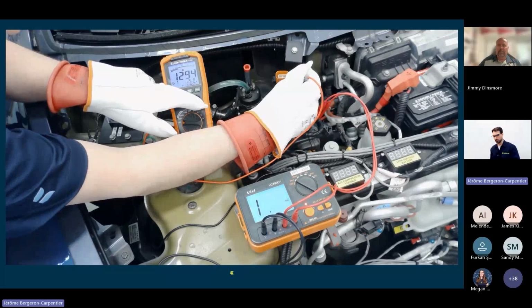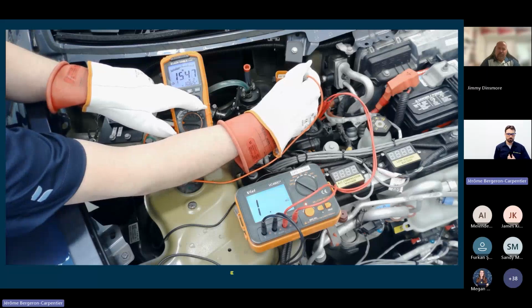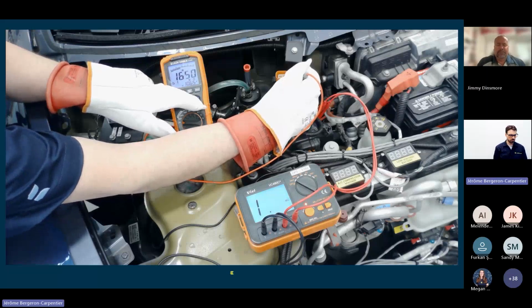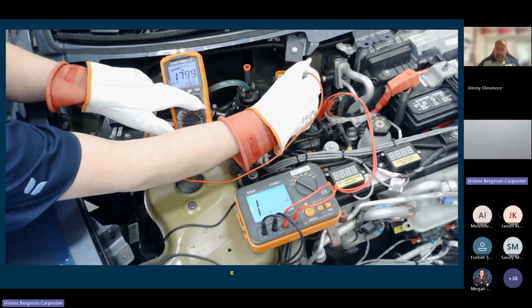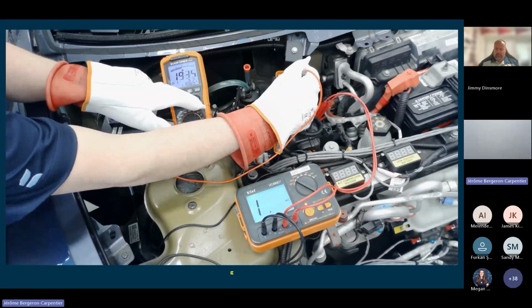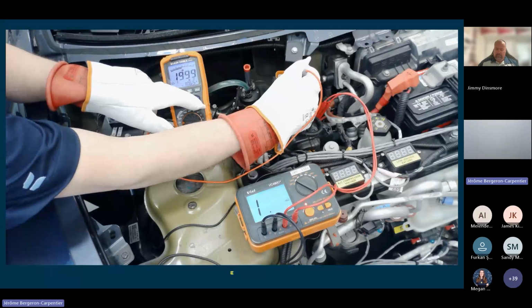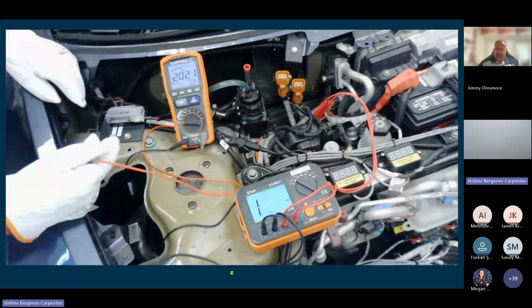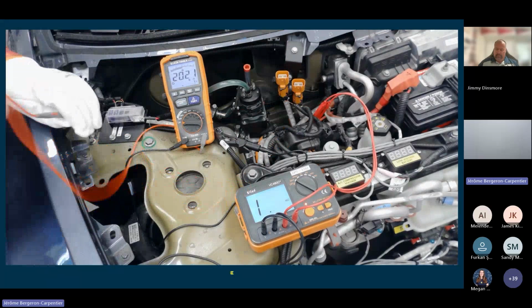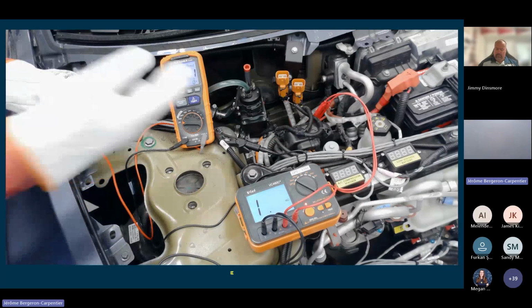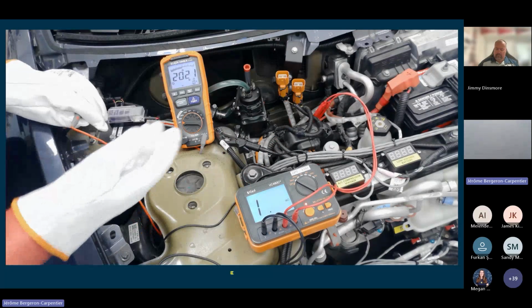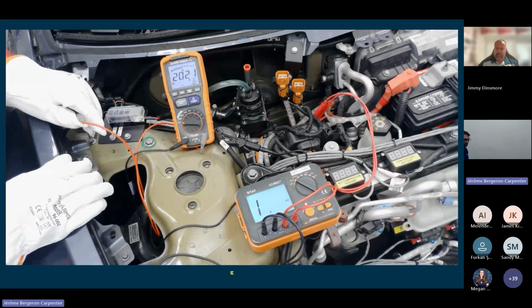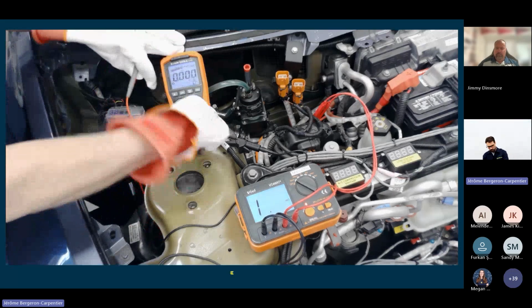So I'm going to put voltage into the AC compressor. Now I've got to remember, I'm going through an inverter, so there are specifications on doing this type of testing. Maybe a little bit more involved. Sometimes we rely more on the codes themselves, but I can see I put it there. Now this is really important. Since there's an inverter controller inside this compressor, there are capacitors inside here. So if I just release this, some people think, okay, well, it failed, we're going to replace the compressor, not realizing they have just charged that compressor with energy.